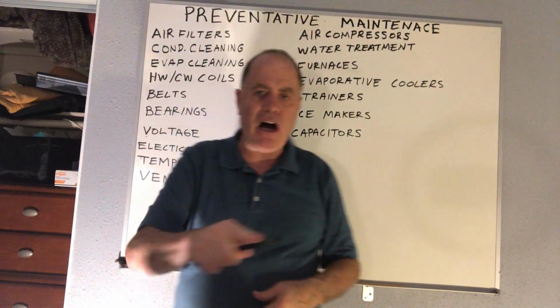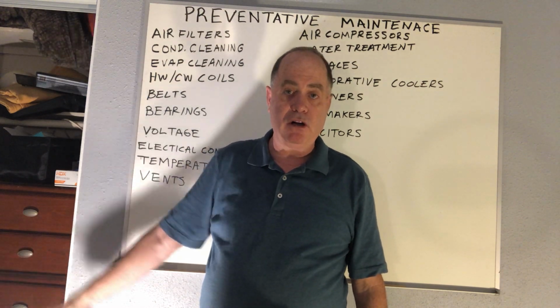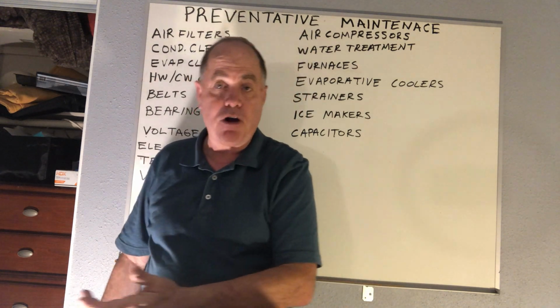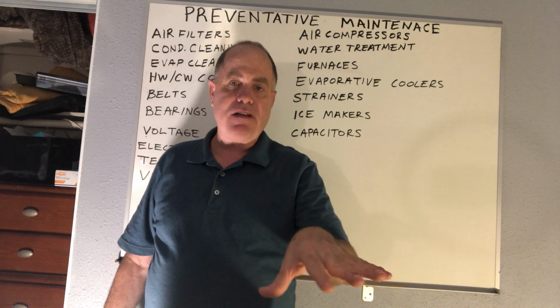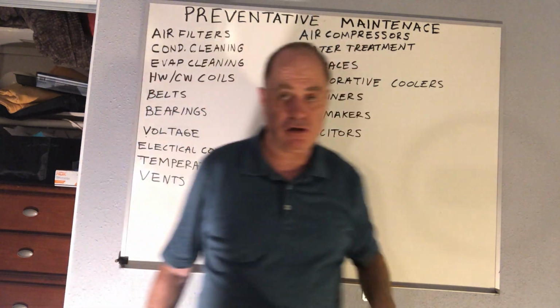So we usually have an auto trap, a float valve really, that takes the water that builds up out the bottom of your air compressor. But they have a drain bypass valve. You should be making sure that you open that and drain any water off as part of maintenance. And then if you do get more than a few drips of water out of there, you'll be like, wait, maybe this auto trap float isn't working well. So that's another thing to check on your air compressors.